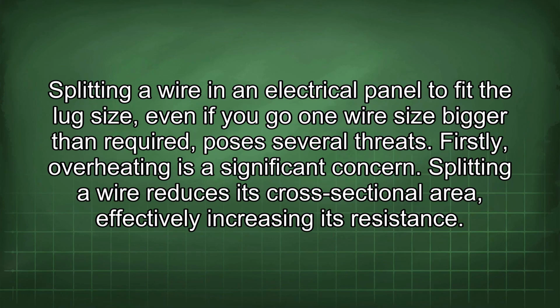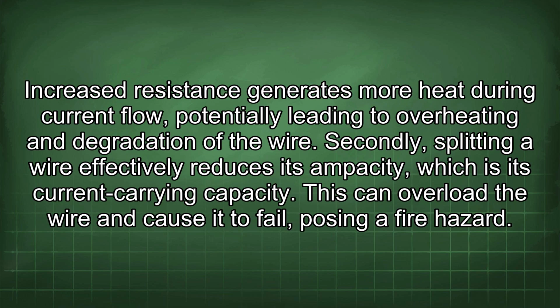Splitting a wire in an electrical panel to fit the lug size, even if you go one wire size bigger than required, poses several threats. Firstly, overheating is a significant concern. Splitting a wire reduces its cross-sectional area, effectively increasing its resistance. Increased resistance generates more heat during current flow, potentially leading to overheating and degradation of the wire.